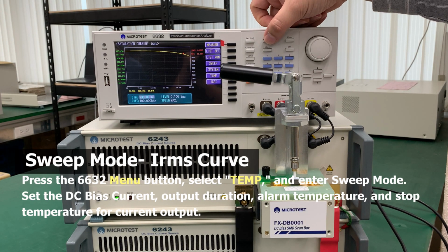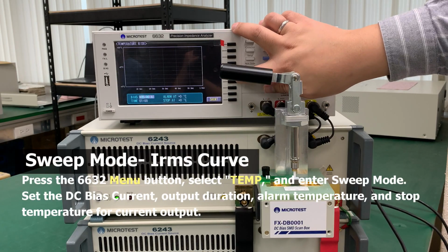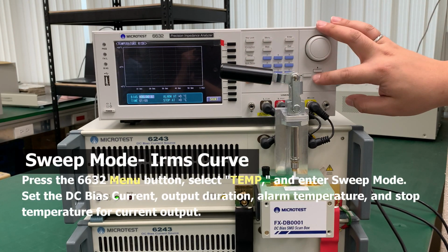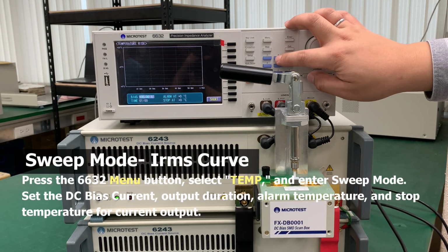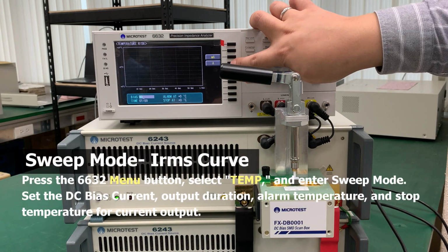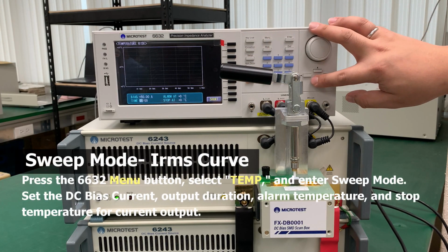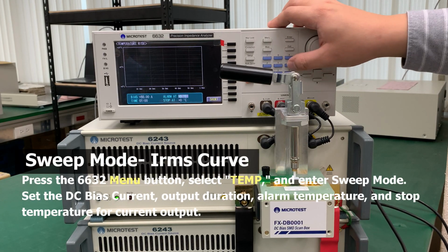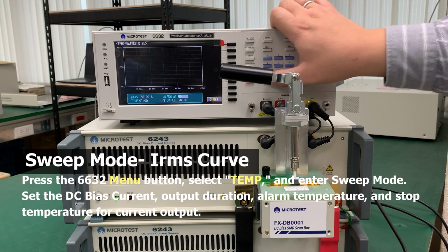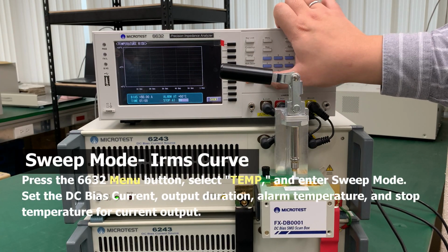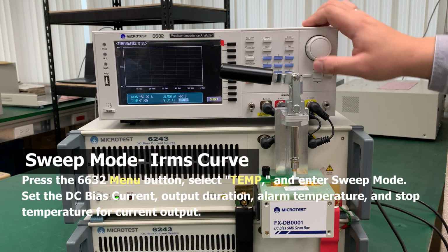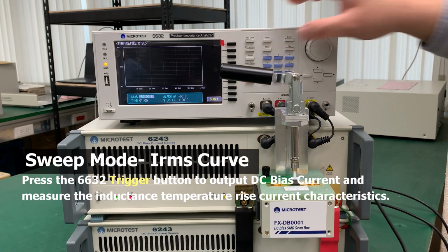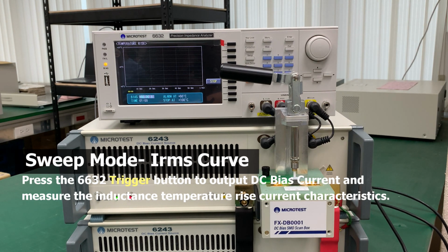Press the 6632 menu button, select Temp, and enter sweep mode. Set the DC bias current, output duration, alarm temperature, and stop temperature for current output. Press the 6632 trigger button to output DC bias current and measure the inductance temperature rise current characteristics.